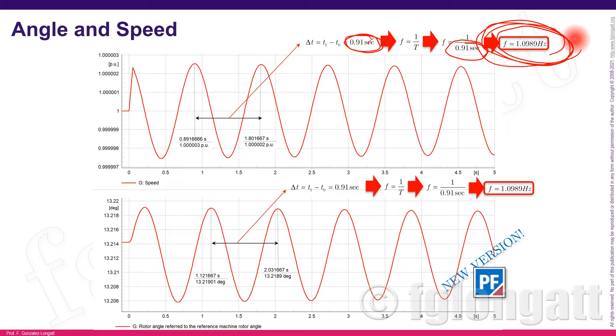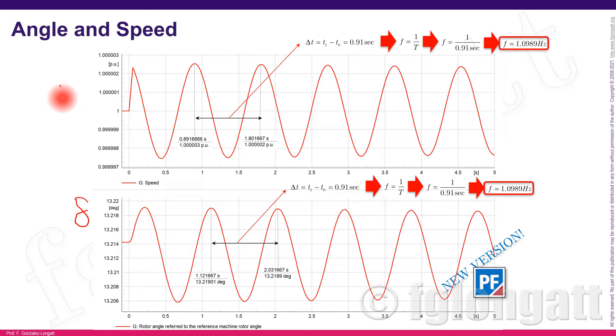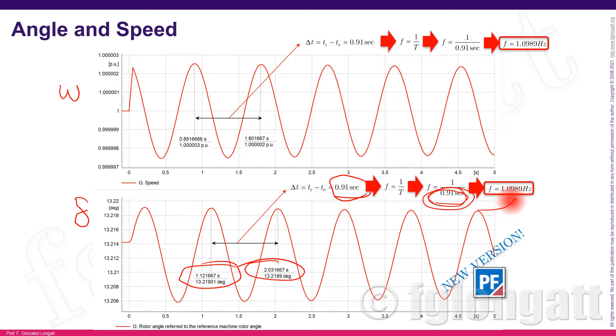Calculating the frequency from the period, the oscillation frequency for this very specific example is 1.0989 Hz. Performing the same exercise on the rotor angle — calculating its period of oscillation — also gives 0.91 seconds, confirming the same oscillation frequency of 1.0989 Hz.